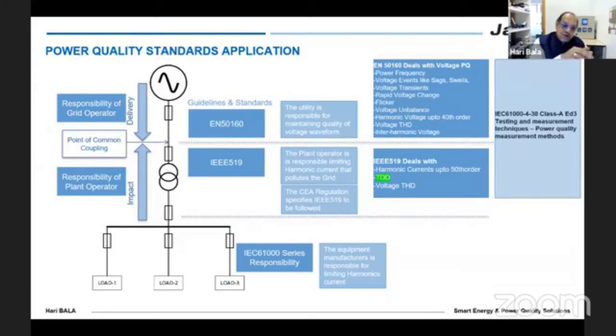Now we know that when the consumer gives so much harmonics, it naturally distorts the voltage. And the same voltage is supplied to the other consumer, isn't it? On the same bus bar or on the same line. Which means the other customer, who is not generating harmonics, is getting a distorted voltage. That is why the utility should manage not only to support the customer who is generating harmonics, but also to adjust their system impedance in such a way that they don't transfer the same voltage quality to the other customer. There is a thin line of difference in how they will have to handle this particular issue, because it's a shared responsibility. That's what IEEE 519 says.